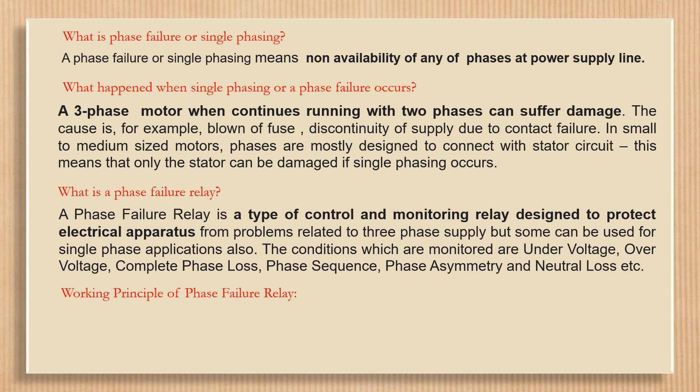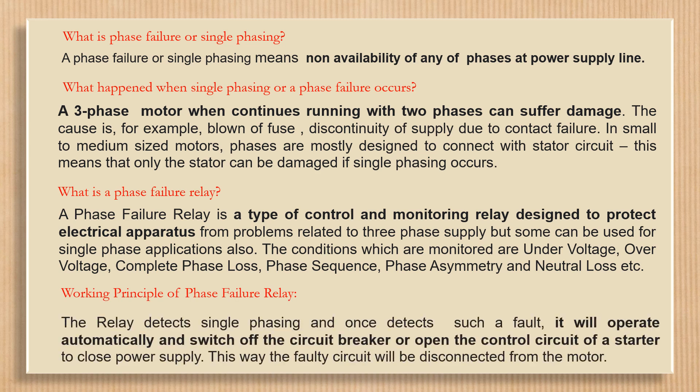Working principle of the phase failure relay: the relay detects single phasing, and once it detects such a fault, it will operate automatically and switch off the circuit breaker or open the control circuit of a starter to close the power supply. This way, the faulty circuit will be disconnected from the motor.